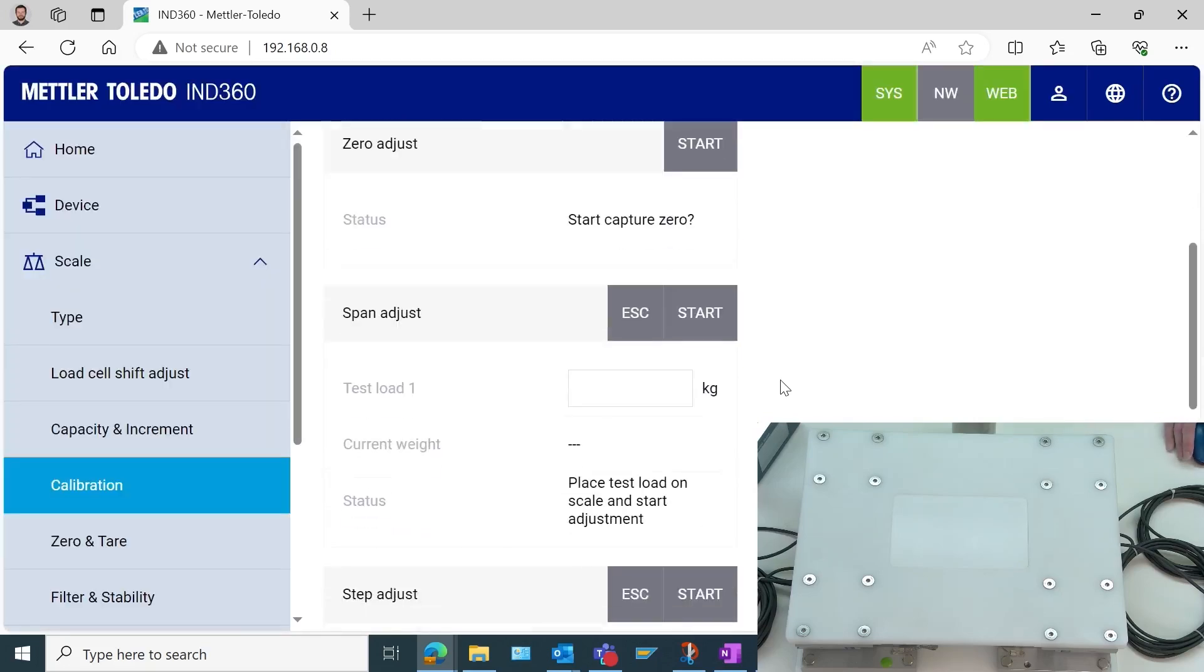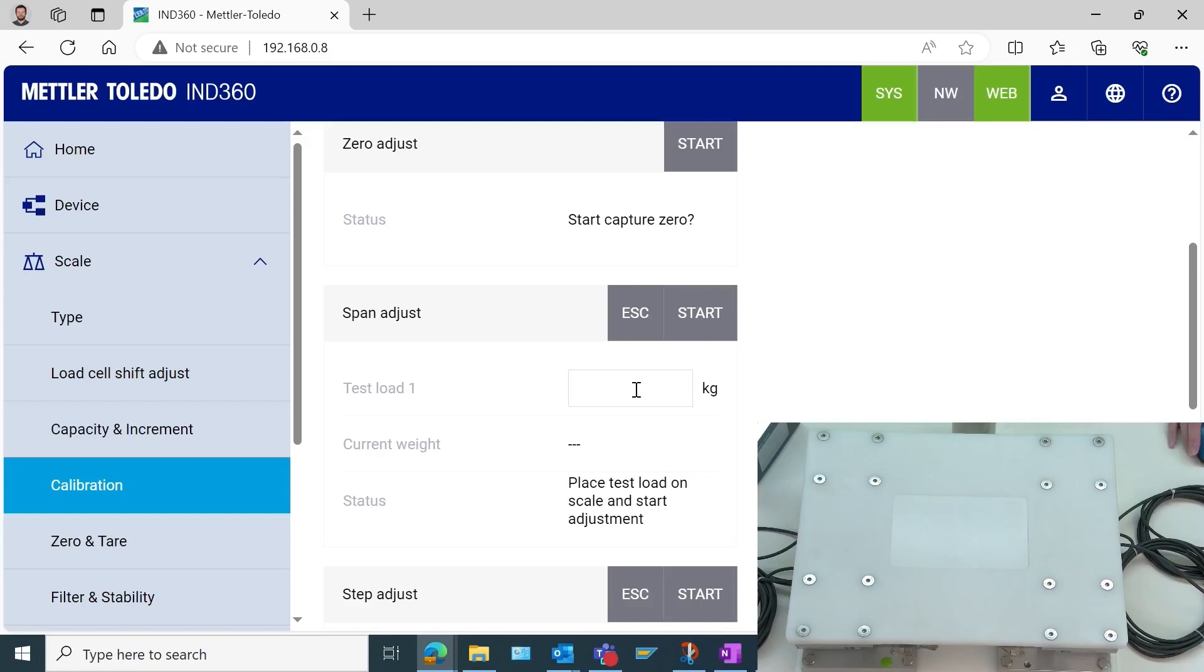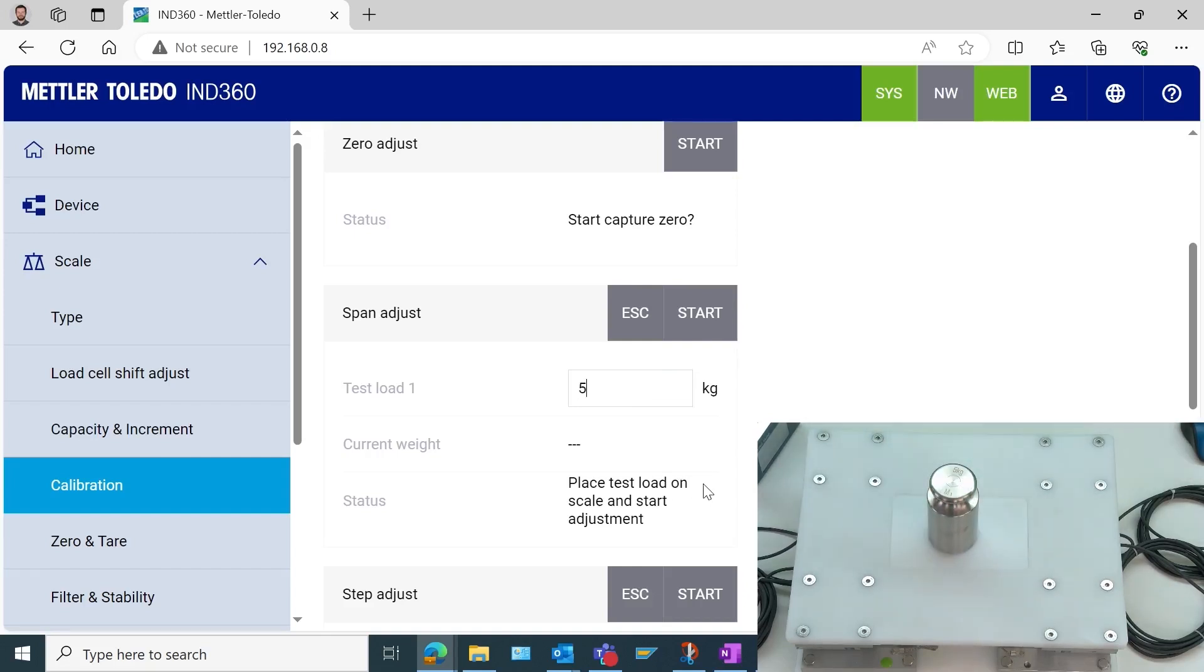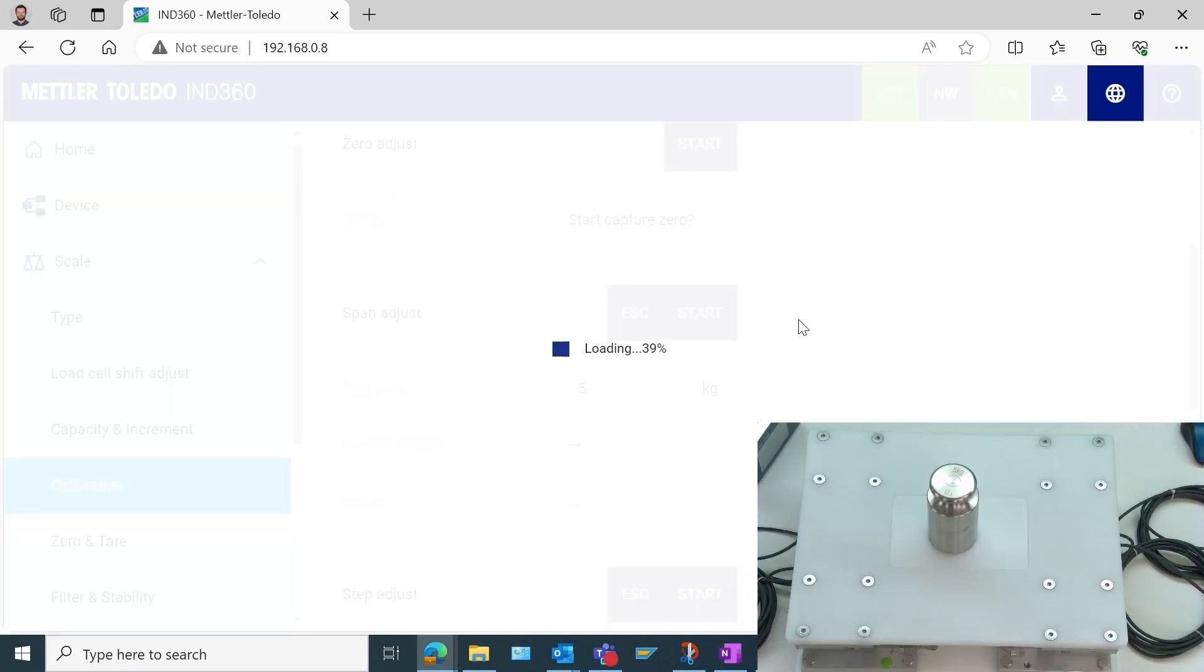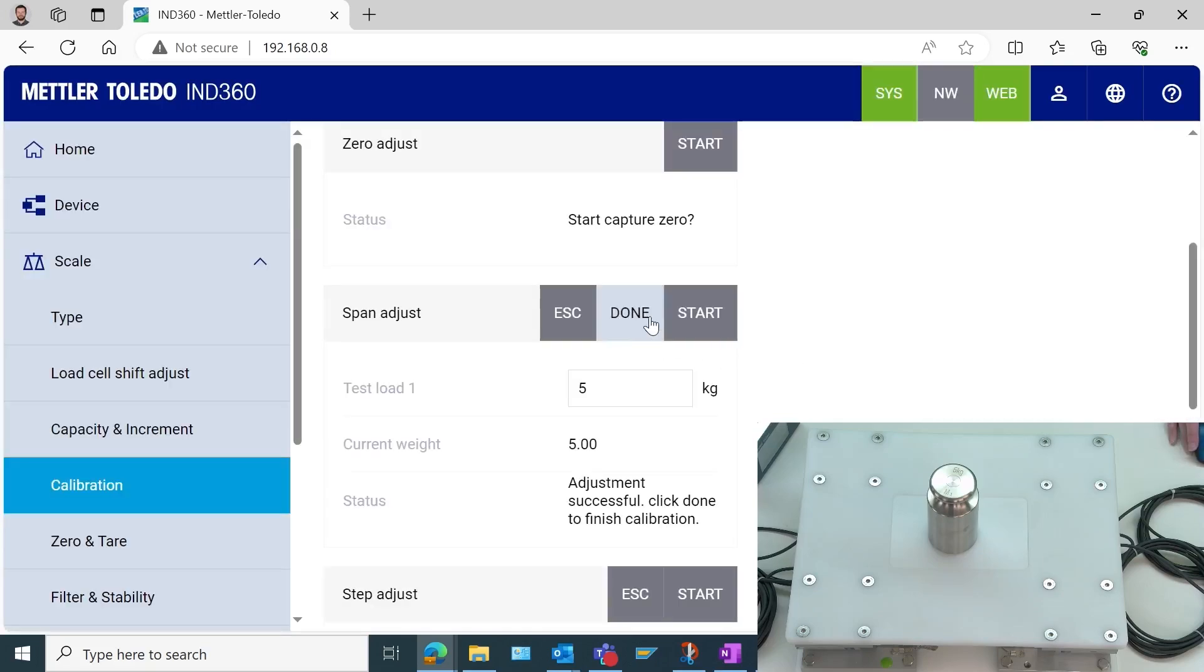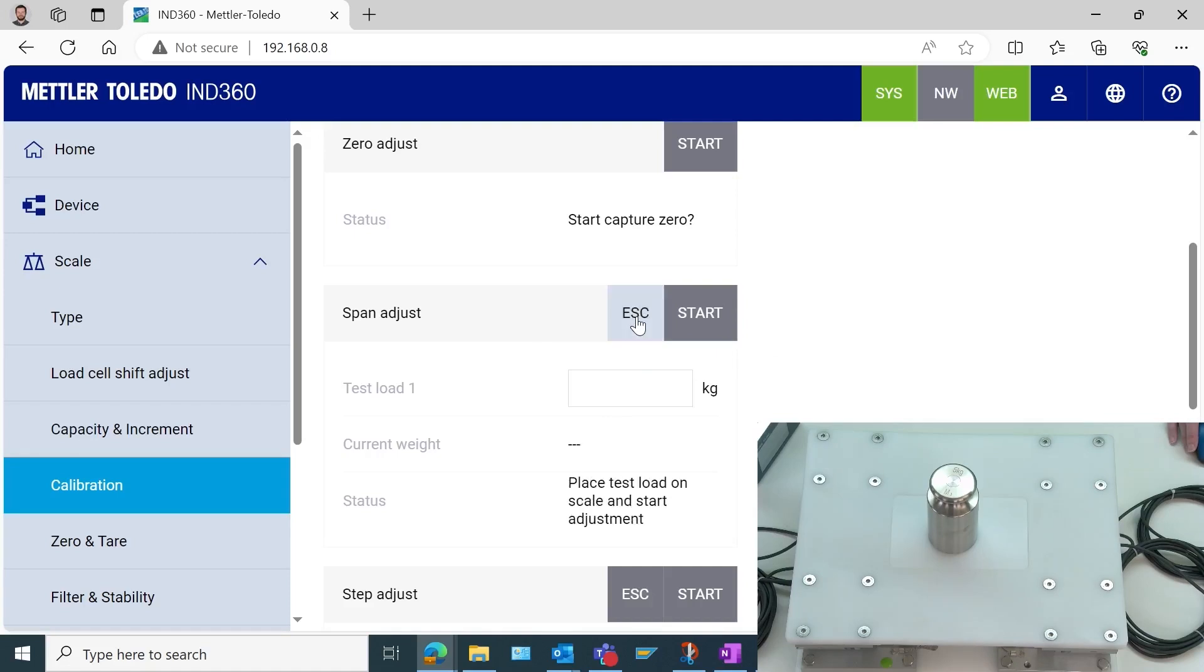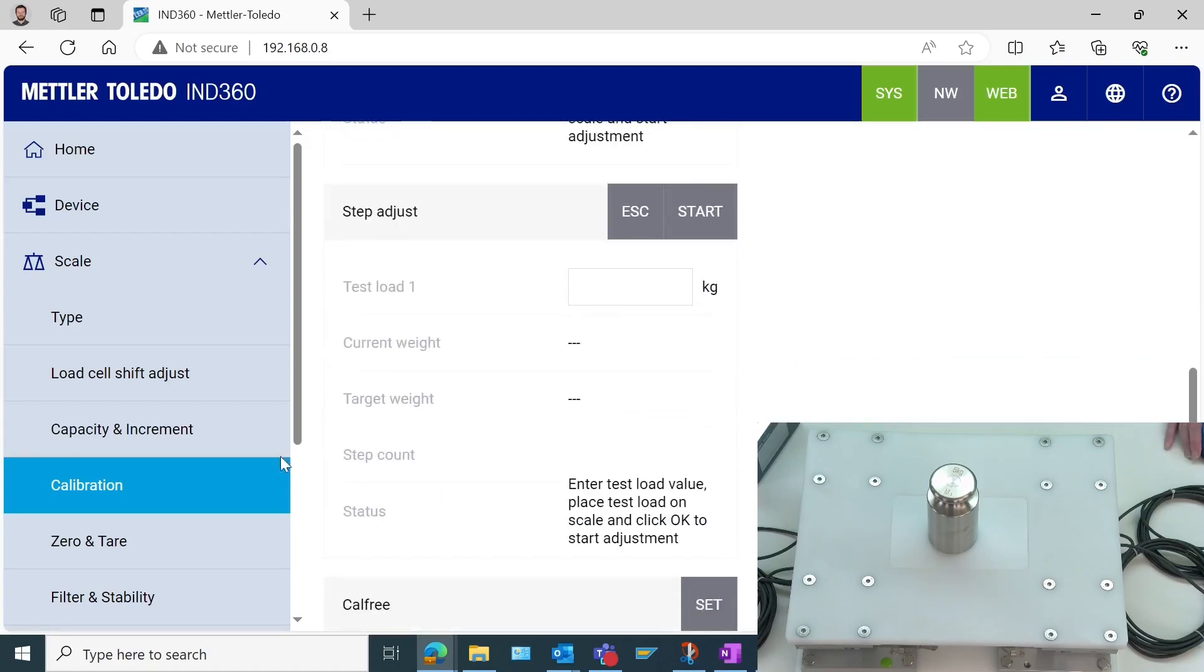Now the next step, we have a few options. We could do a step adjust for incremental calibration. We could do rapid cal. We could do cal free. All of these have their pros and their cons. But what we're going to do is the classic test weight adjustment, which is still the most accurate way to calibrate and perform adjustments. Here I'm going to select 5 kgs and make sure I read that it tells me to place the test load on the scale and then start the adjustment. So I will place that and then select start. It tells me my current weight is 5. I'm happy with that. So I will select done to save that value.